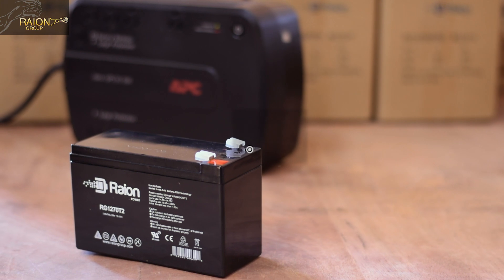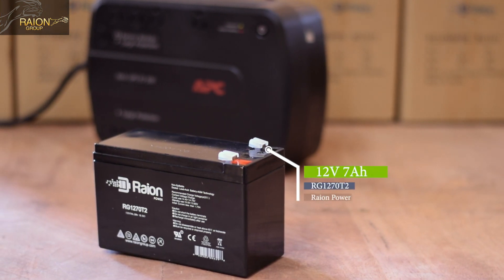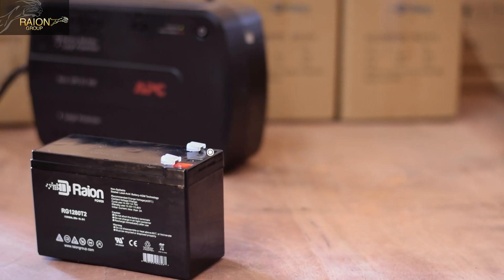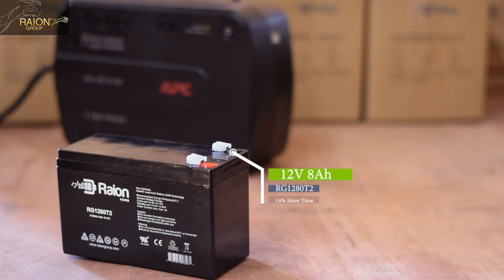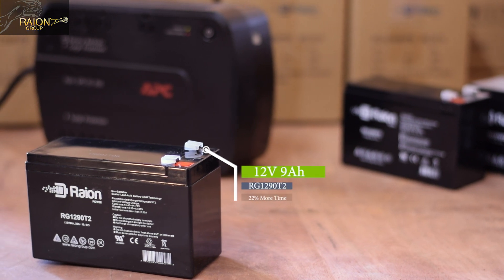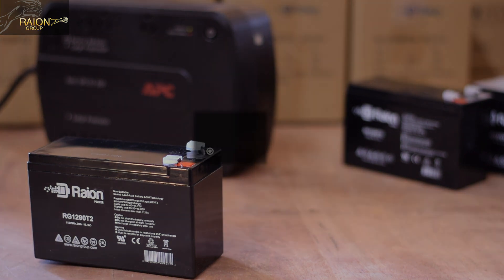The things you'll need to replace your battery in your APC Back-UPS system is a 12V 7Ah RG1270T2 battery from Raion Power — the same size and voltage as the OEM battery. You can opt for a Raion Power 12V 8Ah RG1280T2 battery that will provide an additional 14% runtime, or the 12V 9Ah RG1290T2 battery that will provide 22% additional runtime when compared to the 7Ah.